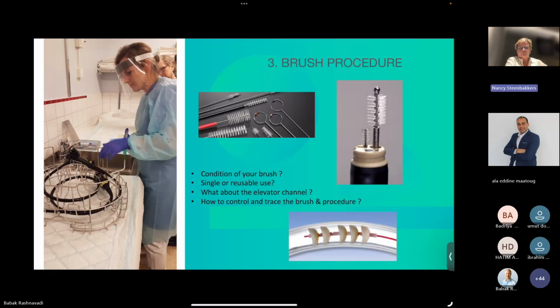Now, the brush procedure is actually another challenge, because the type of your endoscope, or the type of your brush, I mean, will determine your brushing cycle. I'm a very big fan of the pull-through, which is made in New Zealand. They have all kinds of reports that just one pass with the pull-through and your endoscopes are clean. But of course, you have to flush, and you have to flush before you brush. With every brush you have to do that.